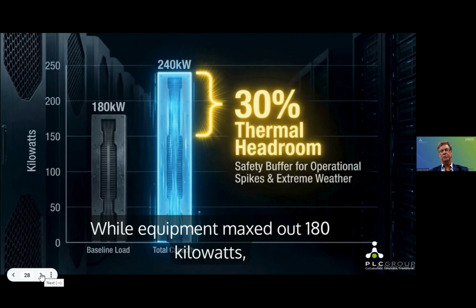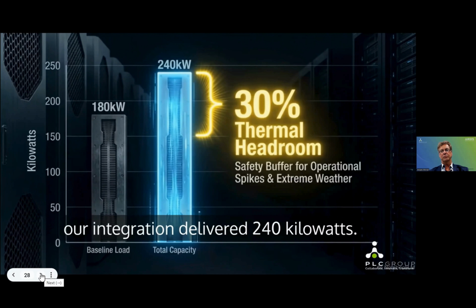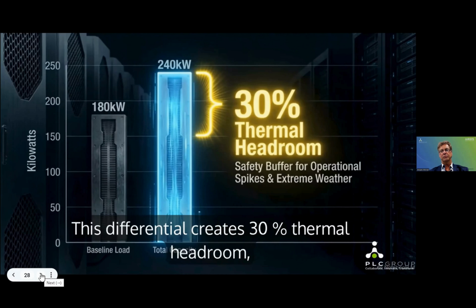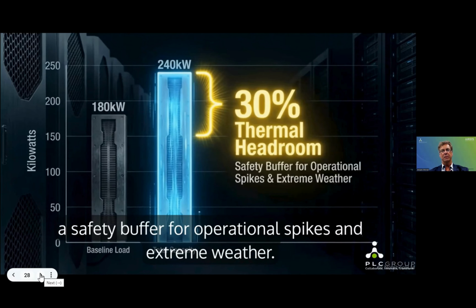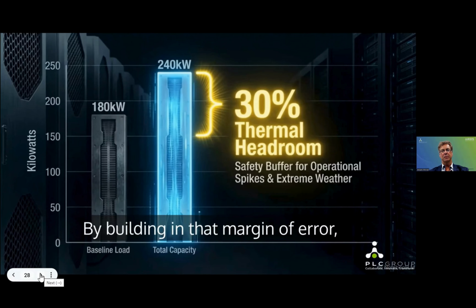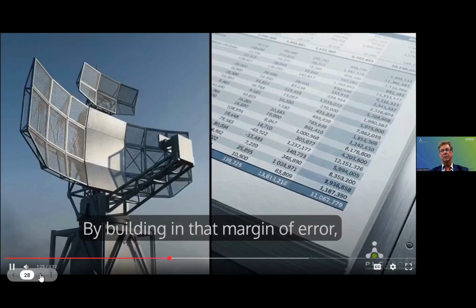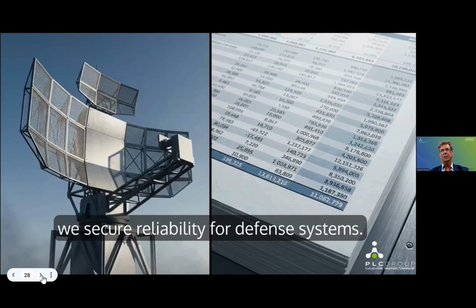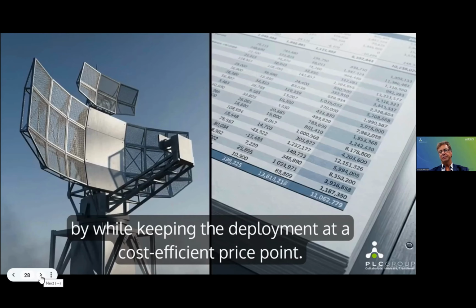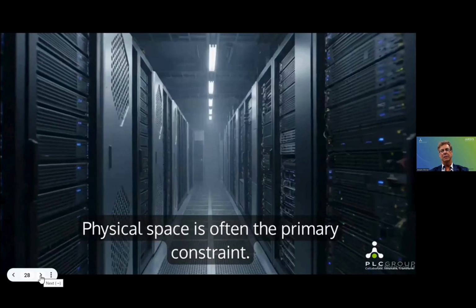While equipment maxed at 180 kilowatts, our integration delivered 240 kilowatts. This differential creates 30% thermal headroom, a safety buffer for operational spikes and extreme weather. By building in that margin of error, we secure reliability for defense systems while keeping the deployment at a cost-efficient price point.